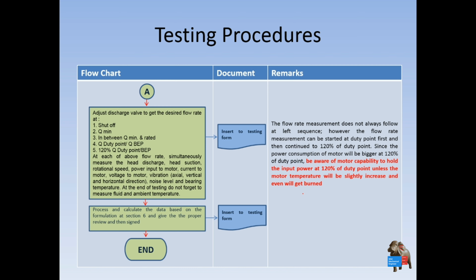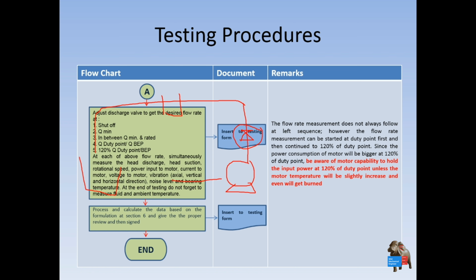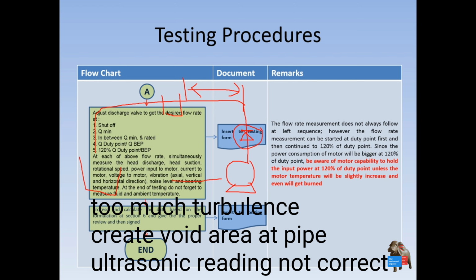Of course, at shut-off there is no flow recorded from the ultrasonic flow meter, because the typical arrangement is like this. For example, you have the pump here, this is the suction, this is the discharge, you have a valve at the discharge, and then you transfer back into the reservoir. Usually the valve is located at least a minimum of 3 times the diameter away. The farther it is, the better. Then you usually have the ultrasonic flow meter here, at a minimum distance of 3 to 5 diameters of the valve, to ensure that the flow of water in the pipe is not really turbulent, so the measurement by the ultrasonic flow meter will be better. With so much turbulence, it's not so good for the real measurement.